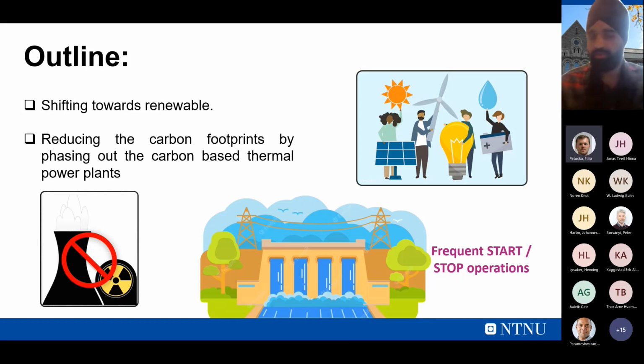So what is this frequent start and stop operation? Hydropower plants usually take very little time to come into the picture as compared to thermal power plants. For a sudden increment of demand, or when we have to shut down some load, these hydropower plants can come into the picture in a very short period of time. But this frequent start and stop operation leads to thermomechanical stresses on the components inside the hydropower plants, especially the materials around the windings of the hydrogenerators. The insulation has a different thermal coefficient of expansion than the copper we are using.